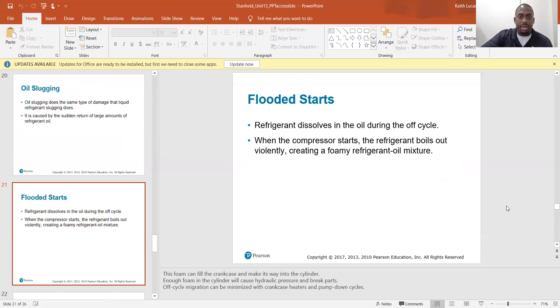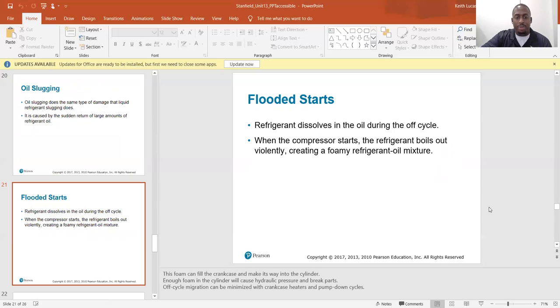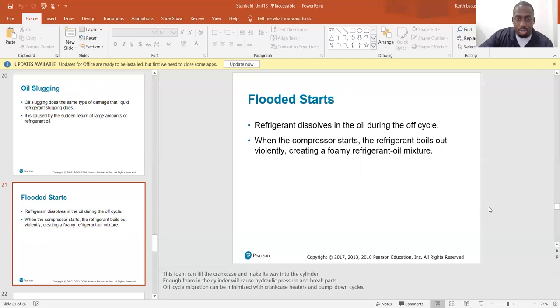Flooded starts: refrigerant dissolves in oil during the off cycle. When the compressor starts, the refrigerant boils out violently, creating a foamy refrigerant-oil mixture. This foam can fill the crankcase and make its way into the cylinder — enough foam in the cylinder will cause hydraulic pressure and break parts, just like having liquid refrigerant in the compressor.